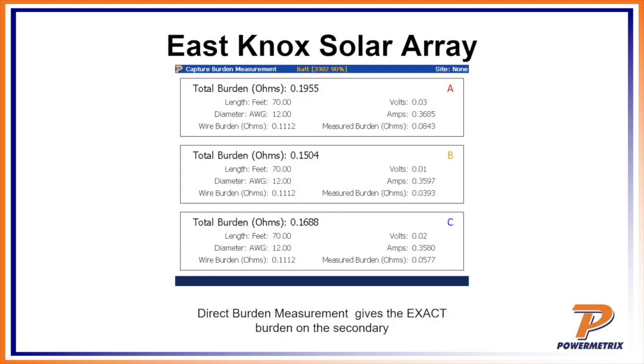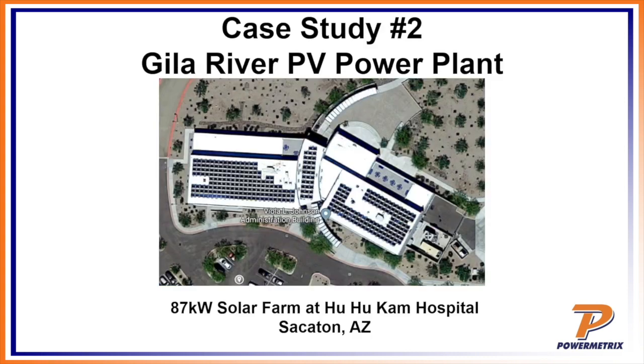We also did a burden measurement—there were no issues we saw as far as the burden measurement. I think it was a 0.5 ohm CT, well under its burden rating. So that was good, that's tight.